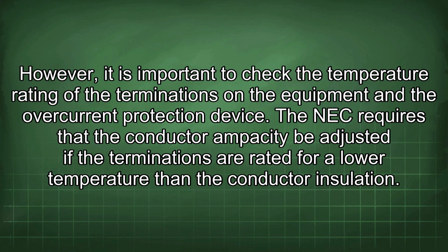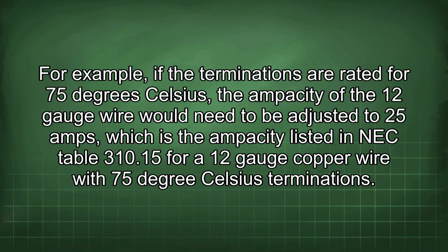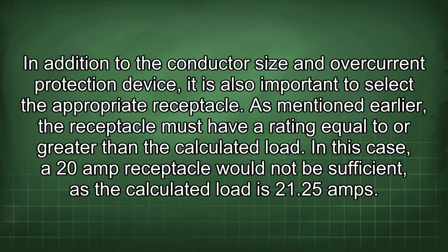However, it is important to check the temperature rating of the terminations on the equipment and the overcurrent protection device. The NEC requires that the conductor ampacity be adjusted if the terminations are rated for a lower temperature than the conductor insulation. For example, if the terminations are rated for 75 degrees Celsius, the ampacity of the 12 gauge wire would need to be adjusted to 25 amps, which is the ampacity listed in NEC Table 310.15 for a 12 gauge copper wire with 75 degrees Celsius terminations. In addition to the conductor size and overcurrent protection device, it is also important to select the appropriate receptacle.